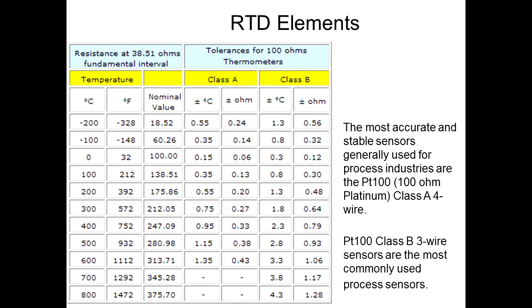When you buy a probe from us, you will get a tag on it that gives the R0. If it says 100.03, it's telling you to take that small error out of your meter when you connect it up, and so you've zeroed out that tiny starting error. You will see a Class B has twice the allowed error as a Class A. So keep that in mind when selecting your sensors.